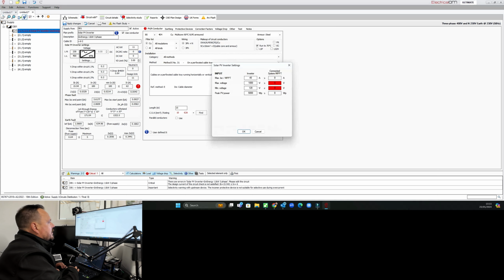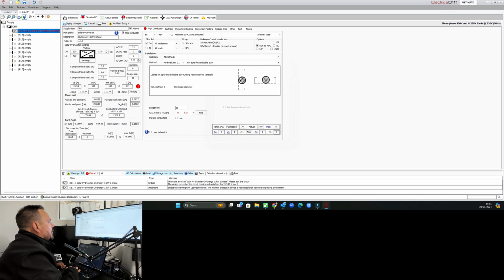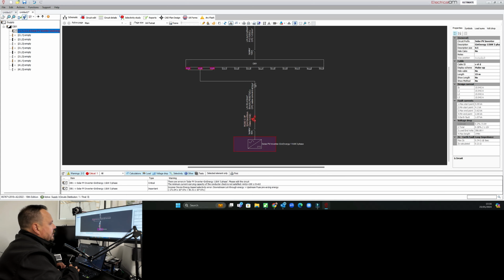Now we can adjust the settings on this as well. So you can see we've got a max voltage of 1000 volts and a minimum voltage of 120. And again, that would depend on the inverter that you're using, so you can get all of that information from the product data sheet. So if we save that and go back in, you can now see we've got our 3-phase final circuit running down, which is 5-core 10 mil steel wire armour, and we've got that RCBO, which is sat there looking after our circuit.